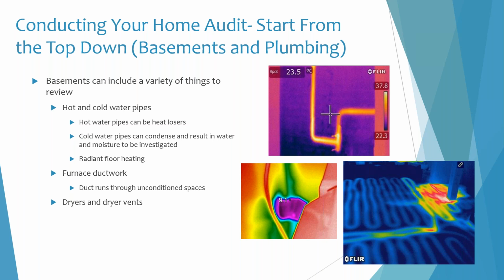But what's also interesting is cold water pipes in a moisture-rich environment can also represent an issue for water and moisture damage. We have been in homes in the past where they have a cold water pipe which runs directly above a suite, like a basement ensuite shower, which was installed afterwards. And unfortunately, the owner wasn't really aware of the powers of condensation at the time. And so what we found through our thermal imaging was that the water condensing on that pipe was actually compromising the drywall and generating a whole bunch of problems, which he had been complaining about upstairs as well.